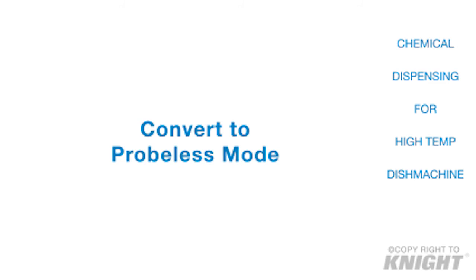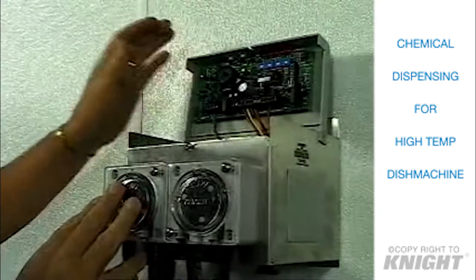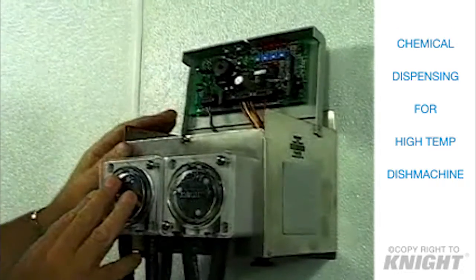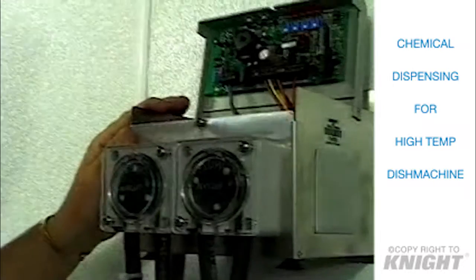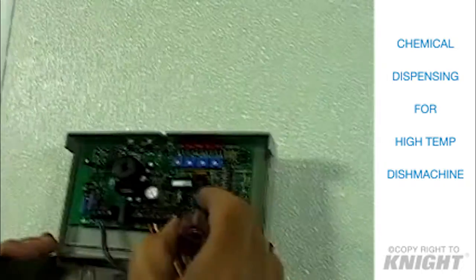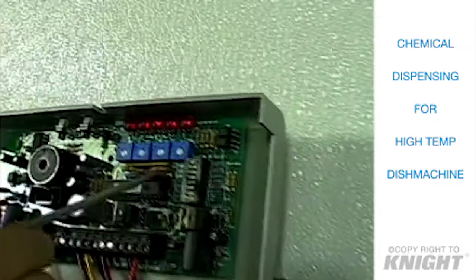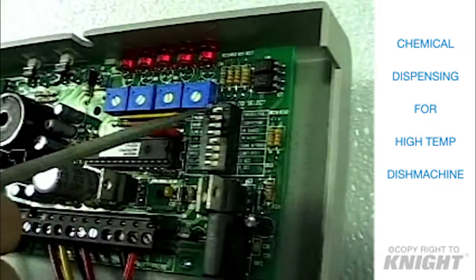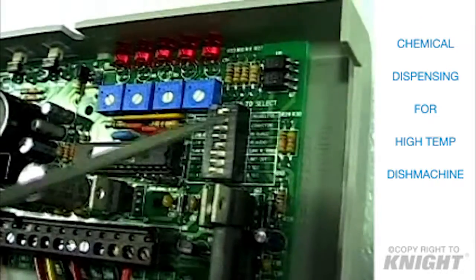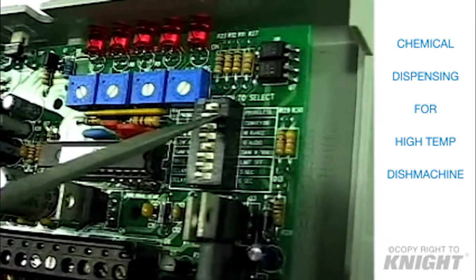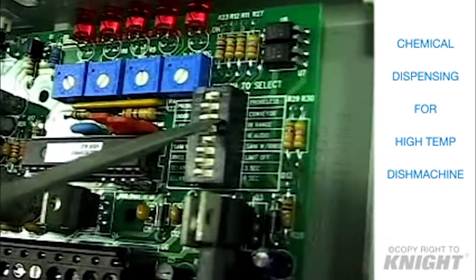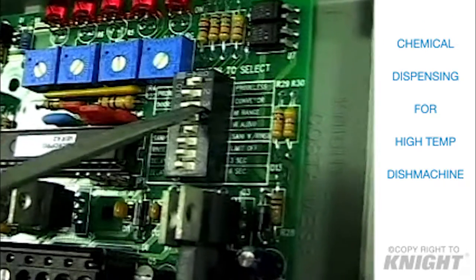Okay, now we've converted this machine, this MicroPro 2, so that we can operate it in probeless mode. So let's just have a look at the settings. What I've done to convert it is I've moved these dip switches a little bit. I've moved the probe setting over to probeless. I'm still working on an AM14, so I'm still in door mode. The low range, high range potentiometer are no longer being used.